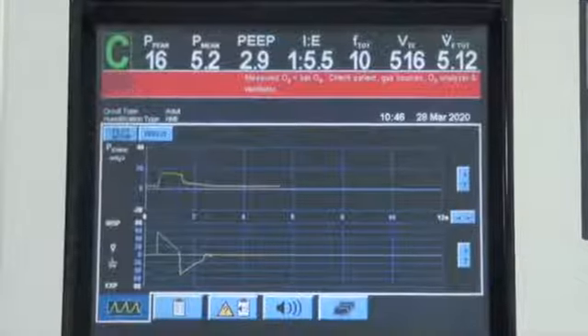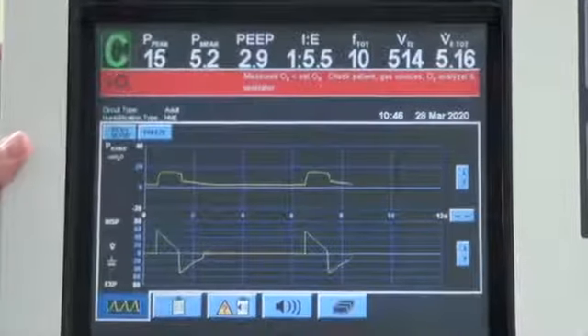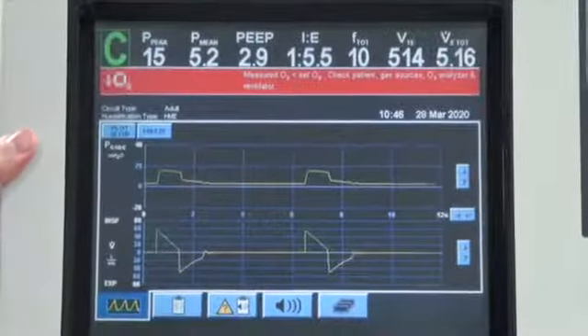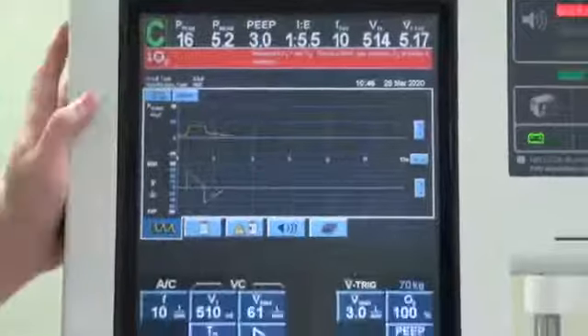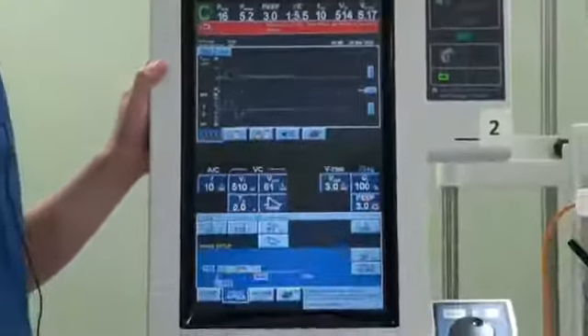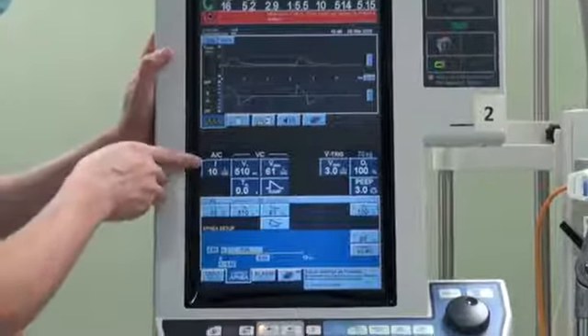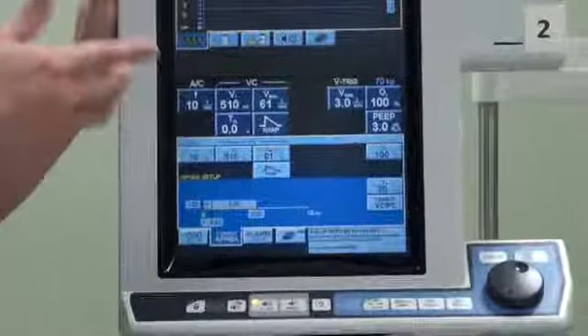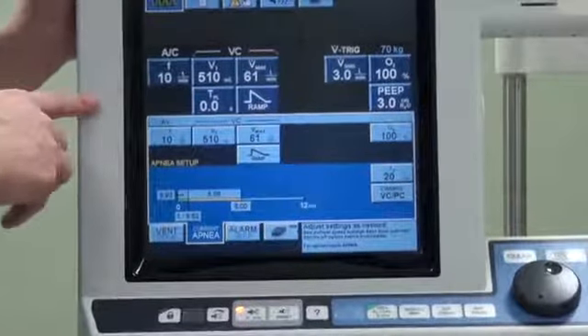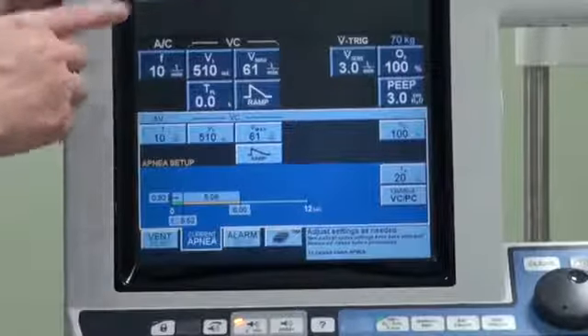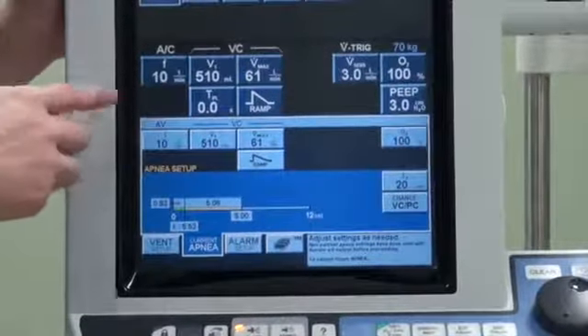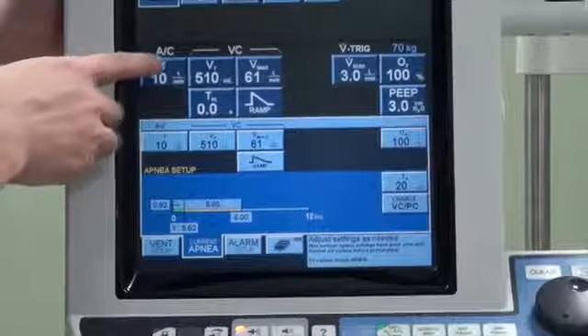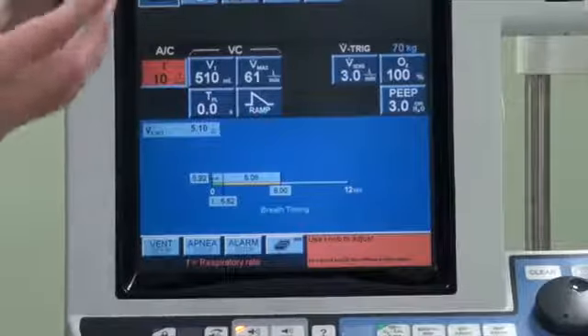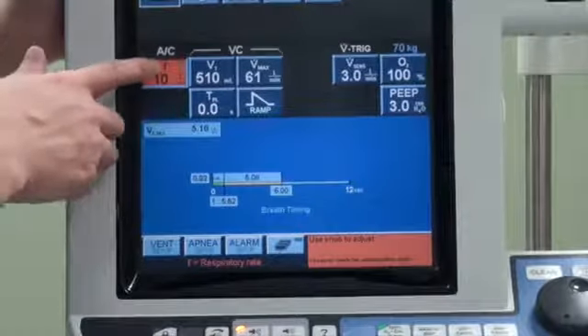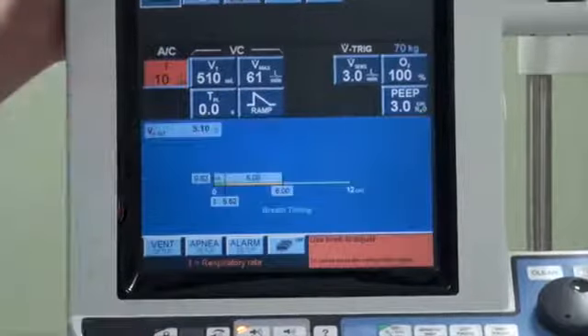The first thing that you want to do when you go into the mode is to set the patient's parameters. The parameter setting is all done in the bottom half, and we will go from left to right to explain what these buttons mean. The first button is F, or the frequency. That will be the respiratory rate that you set for the patient. If the patient has no respiratory drive at all, the machine will cycle every couple of seconds based on what you set as your frequency. So if you set at 10, every 6 seconds, the machine will deliver that breath. To select the buttons, you give a press and it will be highlighted. Once this is highlighted, you can turn the dial to change the parameters that you set.